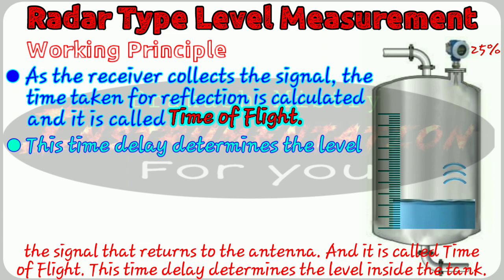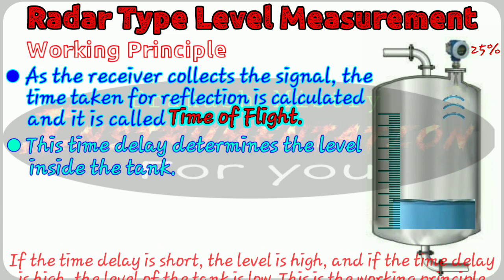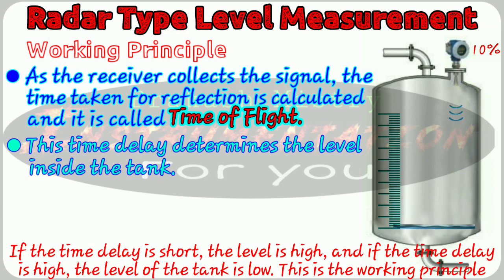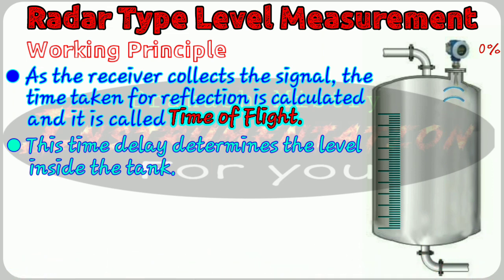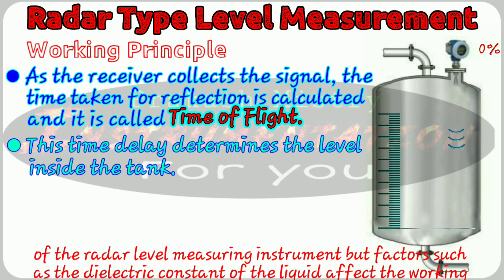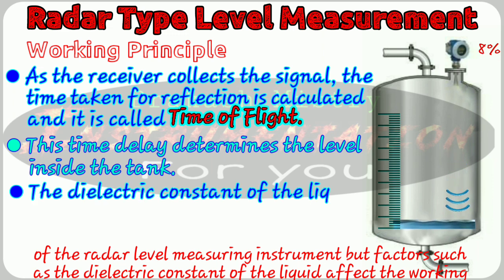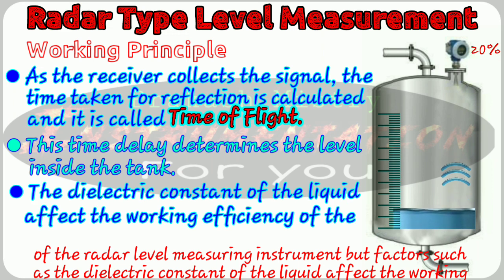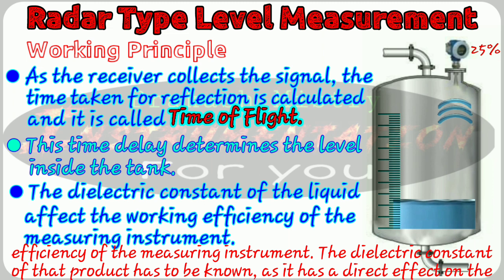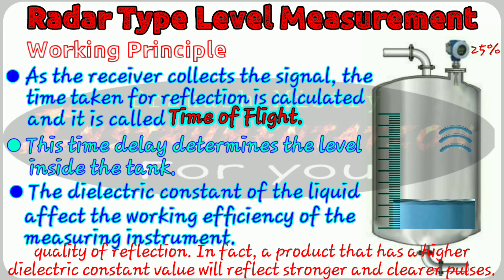This time delay determines the level inside the tank. If the time delay is short, the level is high; if the time delay is high, the level of the tank is low. This is the working principle of radar level measuring instruments. However, factors such as the dielectric constant of the liquid affect the working efficiency of the measuring instrument. The dielectric constant of the product must be known as it has a direct effect on the quality of the reflection.